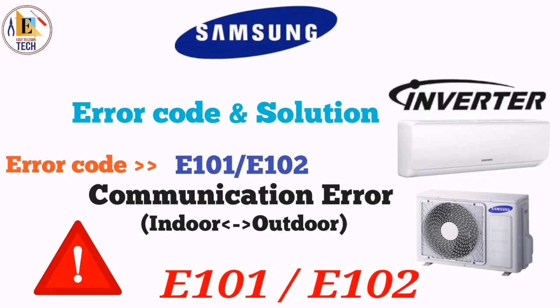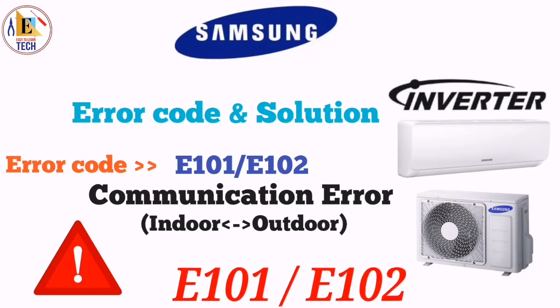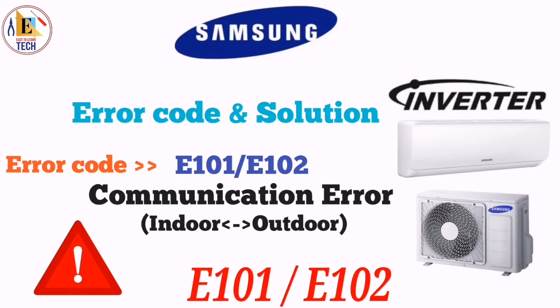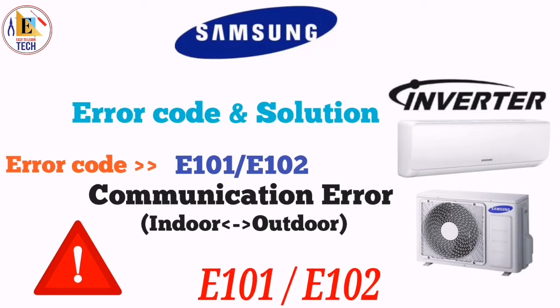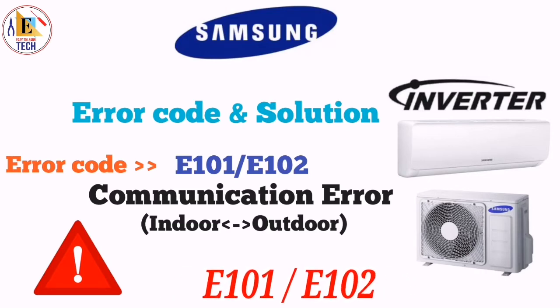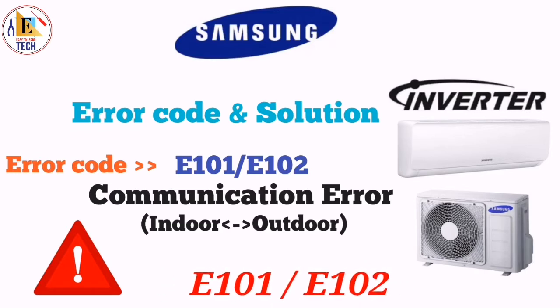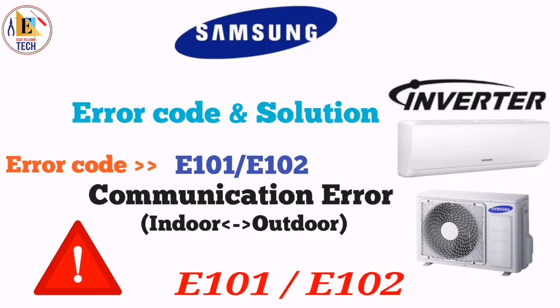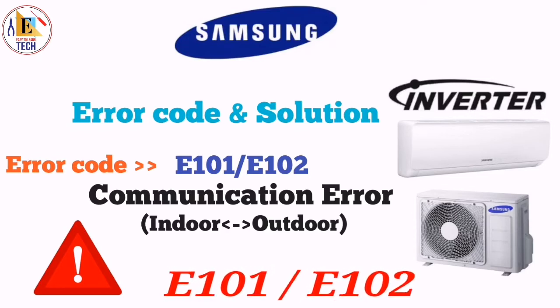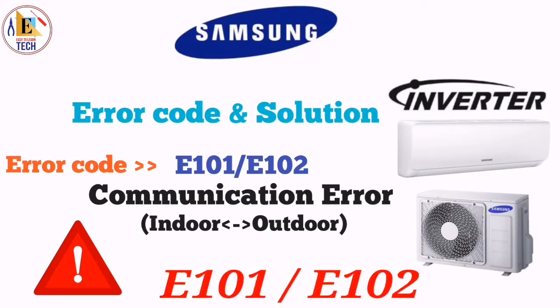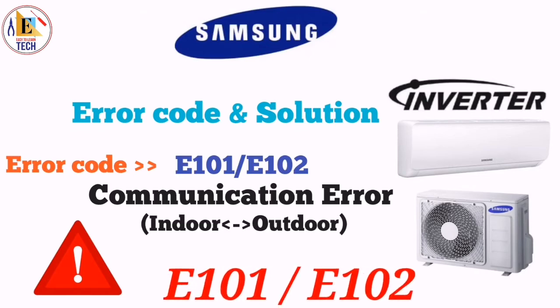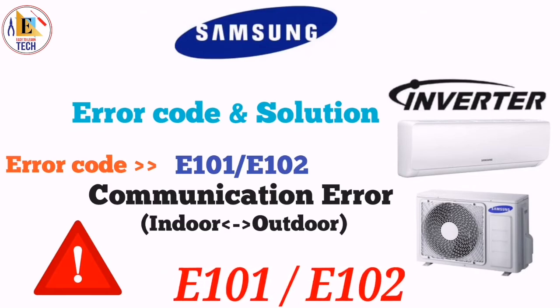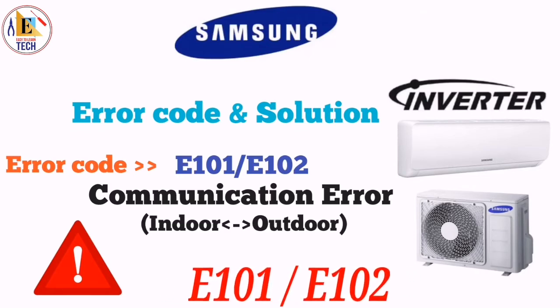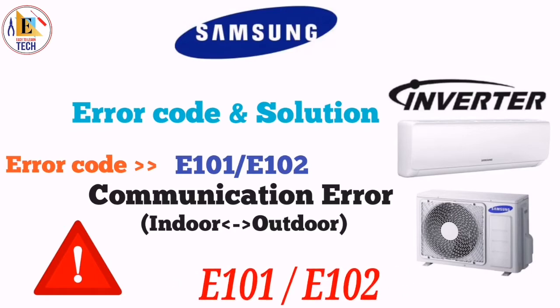If your cable is connected properly, then you have to check if your power cable and communication cable are getting crossed. Because if the power cable and communication cable are crossed, at that time the communication between indoor and outdoor gets mismatched. For the troubleshooting process, first of all, put your system off. Then you have to start it again and check if the communication error occurs again or not. If it occurs again, then you have to check whether your communication cable and power cable are connected properly or not.